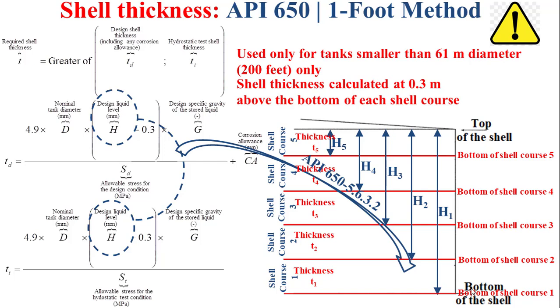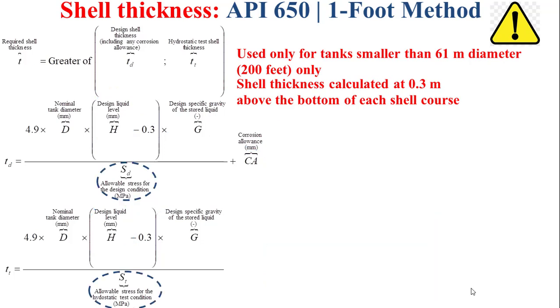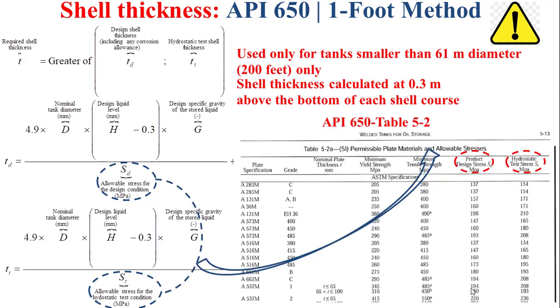For the allowable stresses, we have the allowable stress for the design condition sd and the allowable stress for the hydrostatic test condition st. These are determined directly based on the API 650 standards using Table 5-2, depending on the material of the plate.